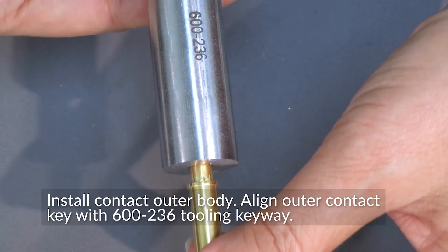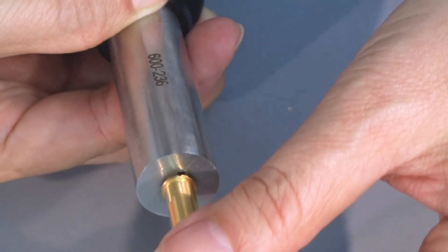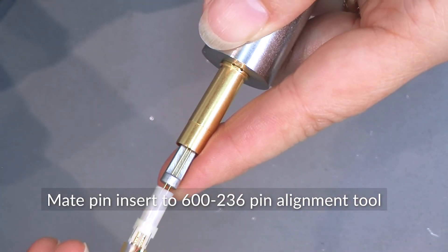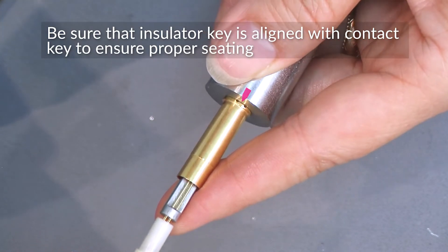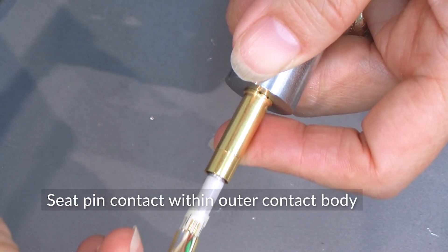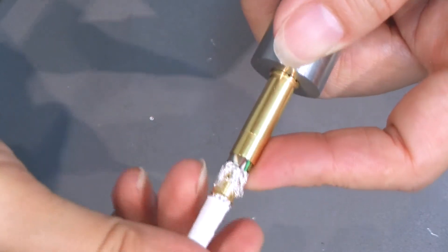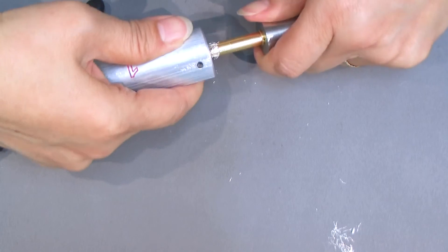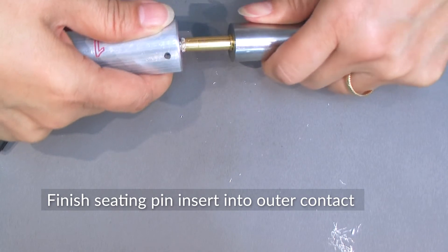To install the outer contact body, align the contact's key with the tool's keyway. Mate the pin insert to the pin alignment tool, ensuring the insulator key is aligned with the contact key for proper seating. Set the pin contact within the outer contact body. Then clamp the insertion tool around the cable — this tool allows firm and even pressure when pushing the assembly together. Push together to finish seating the pin insert into the outer contact.